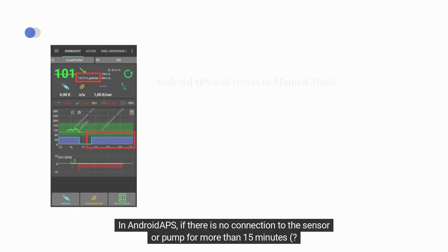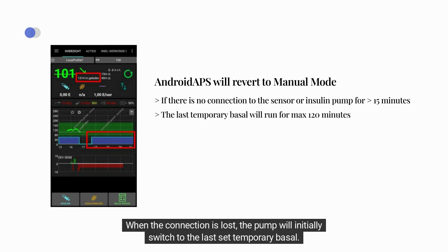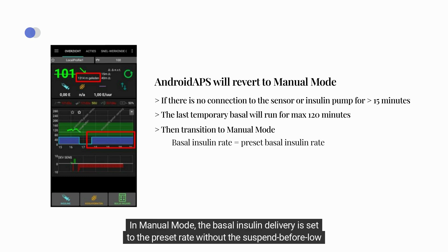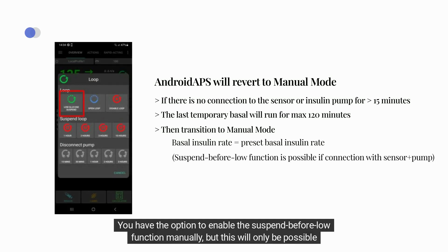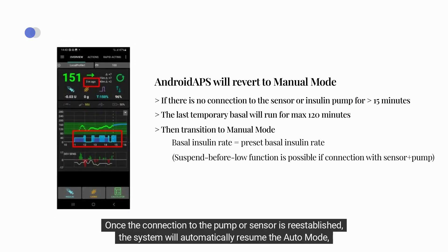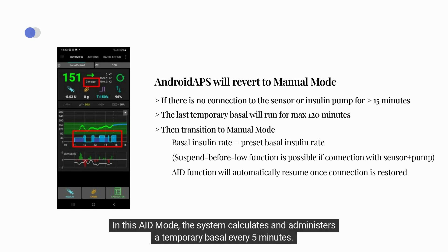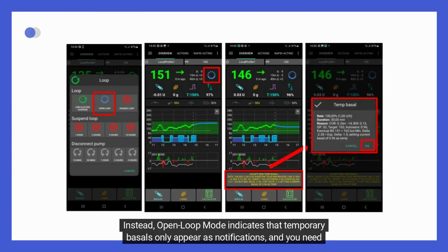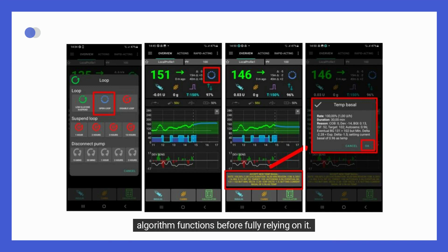Revert. In Android APS, if there is no connection to the sensor or pump for more than 15 minutes, the system will revert to manual mode. When the connection is lost, the pump will initially switch to the last set temporary basal, and after a maximum of 120 minutes it will transition to manual mode. In manual mode, basal insulin delivery is set to the preset rate without the suspend-before-low function. Once the connection is re-established, the system will automatically resume auto mode — automated insulin delivery in Android APS — where it calculates and administers a temporary basal every 5 minutes. Open loop mode in Android APS indicates that temporary basals appear only as notifications and must be confirmed manually, and is recommended for users new to Android APS.